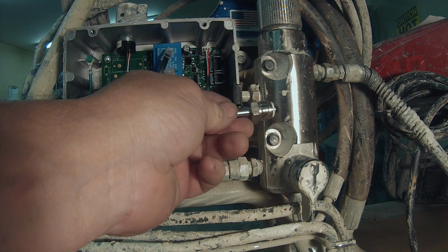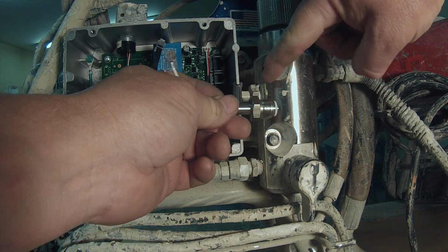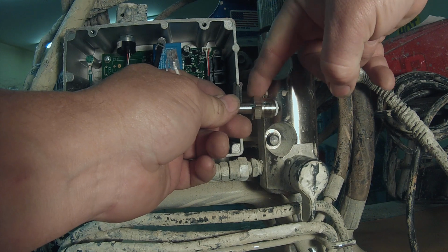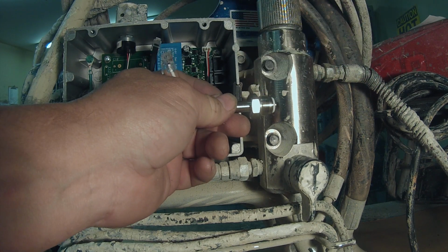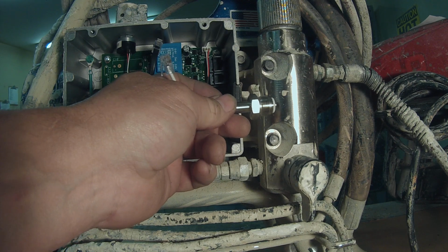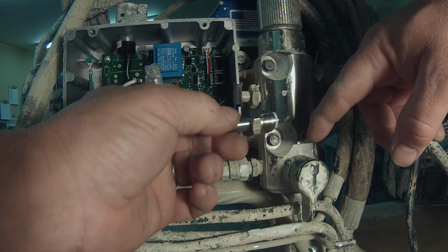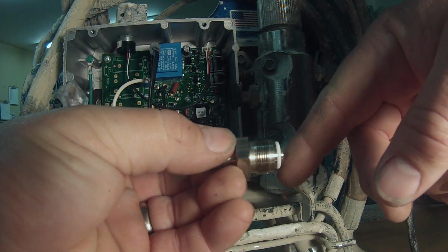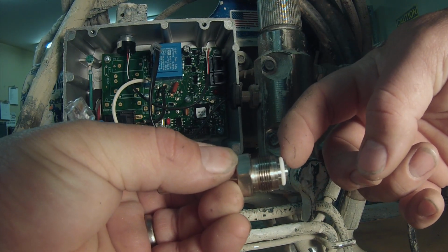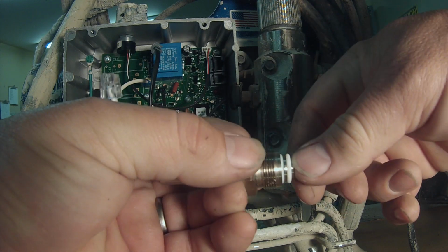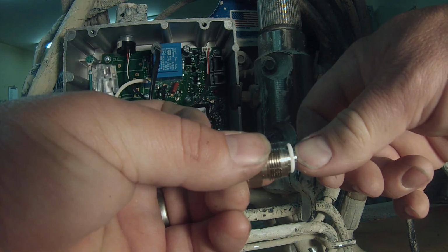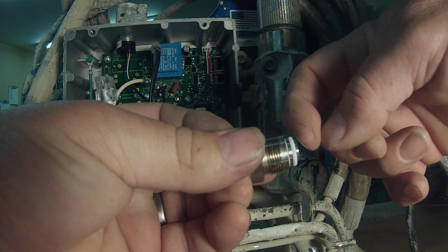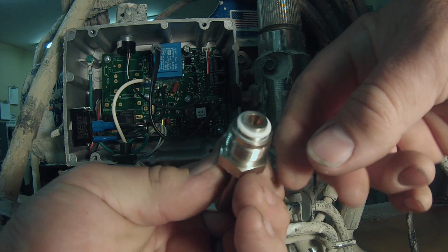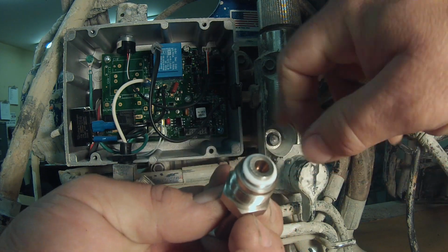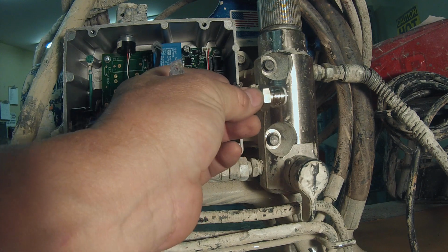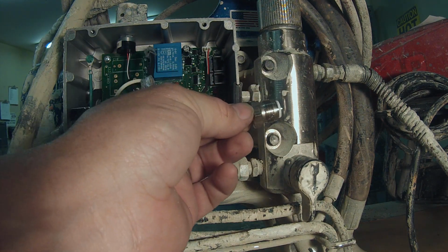Now at that point, you're going to have to force this collar up into the hole, tighten it by finger until you can't tighten it anymore. Once you've got it tight by finger, you're going to tighten it completely up with the wrench. You want it good and snug. Now when you take the old one off, this collar is going to be pushed all the way up over the gasket. There's two gaskets. The first one here you won't be able to see because it's going to be covered. The second one, when the collar is pushed all the way forward, if you look in the end, you'll see the white gasket. Make sure the white gasket comes out, because you don't want to put this in with two gaskets on the end, because it will not seal and it will leak.